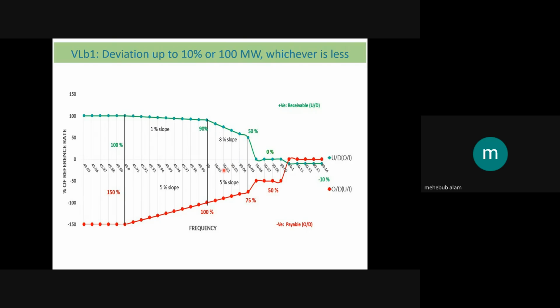So see that if the frequency is increasing, underdrawal is encouraged. In a similar fashion, in case of low frequency, if there is overdrawal, there will be a 150% penalty, 150% of the rate. And similarly, for the next frequency range, 49.9 hertz to 50 hertz, if there is a shortfall, meaning overdrawal, the frequency is already low, but in that low frequency range the generator is short. Generation is short, so they will be penalized at the rate of 100%.